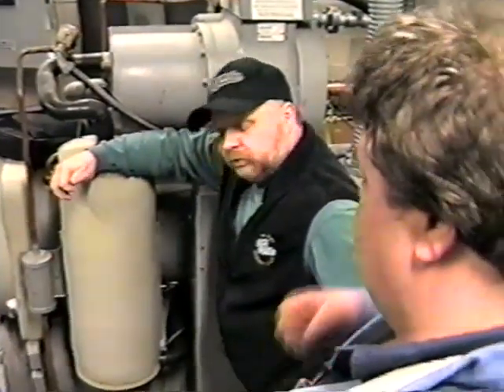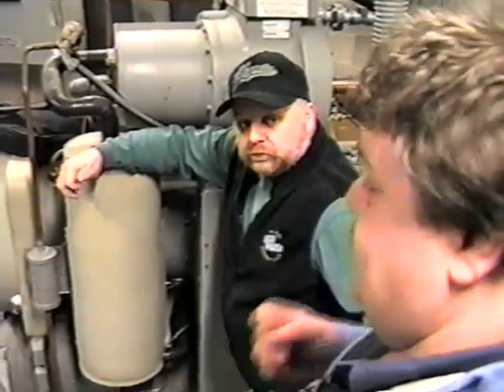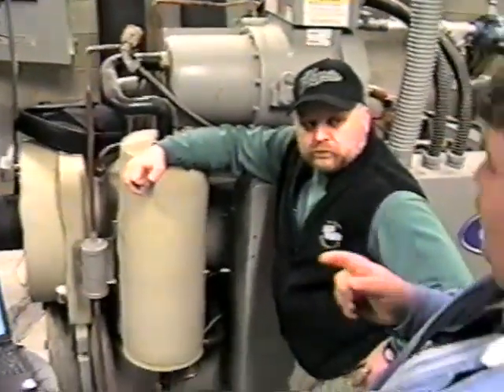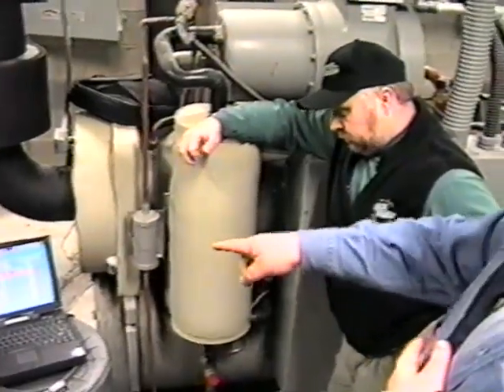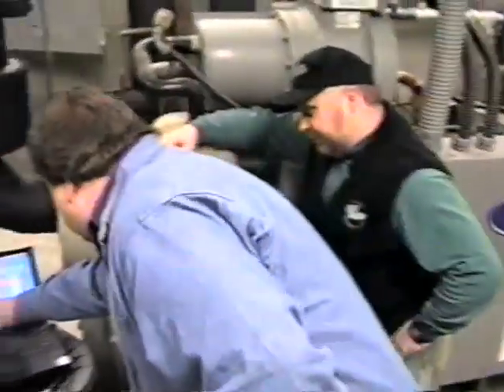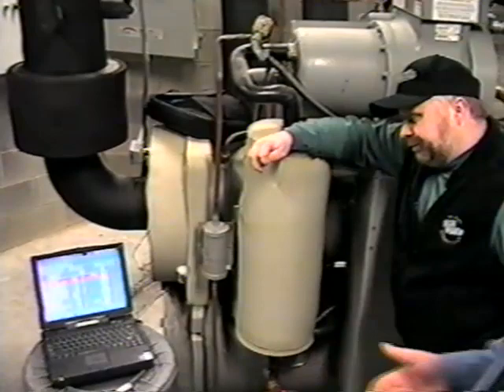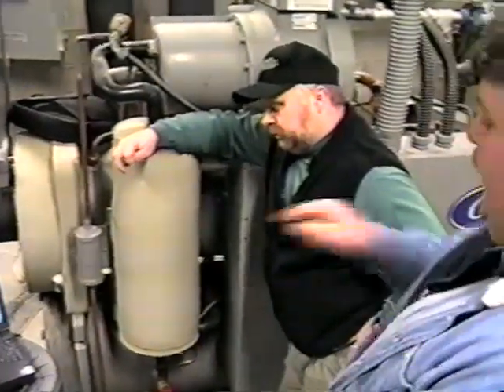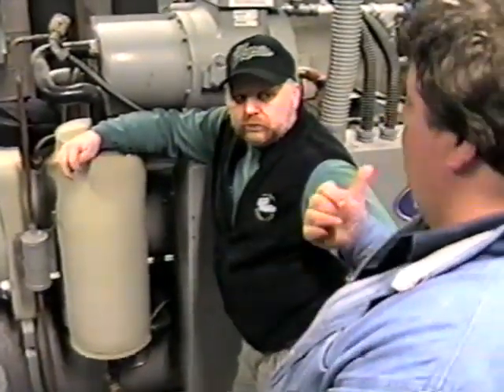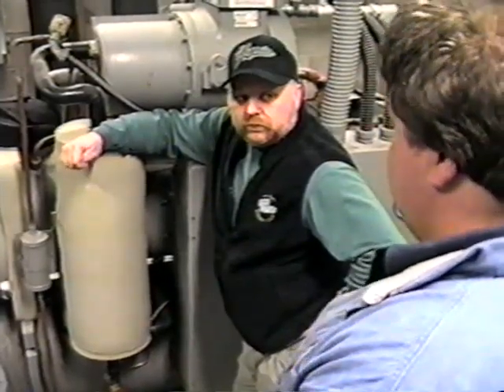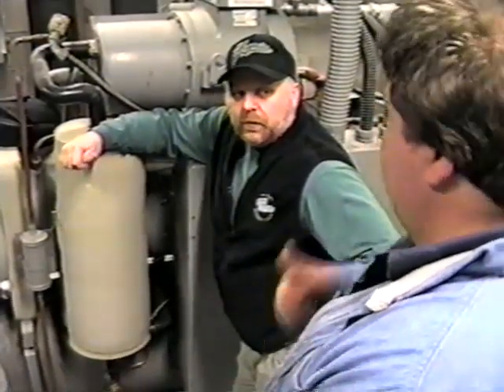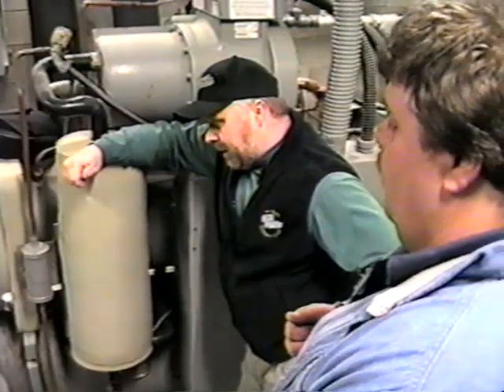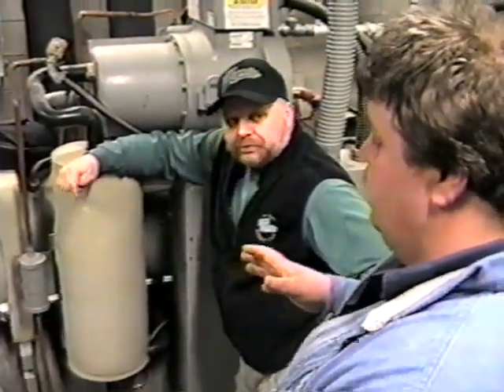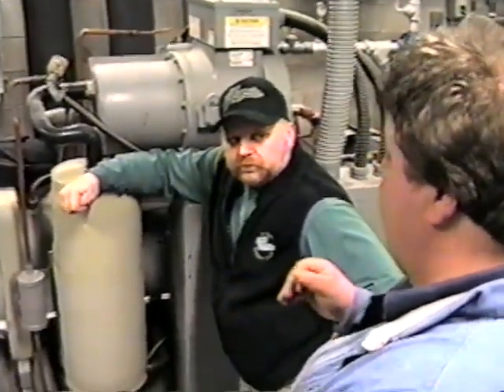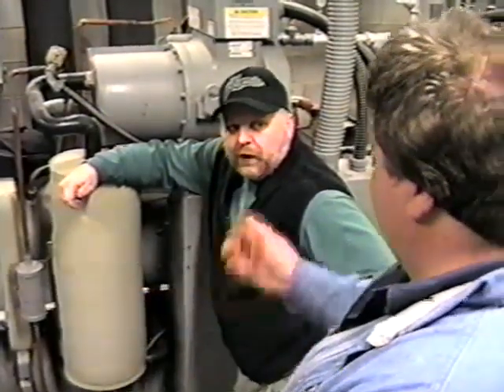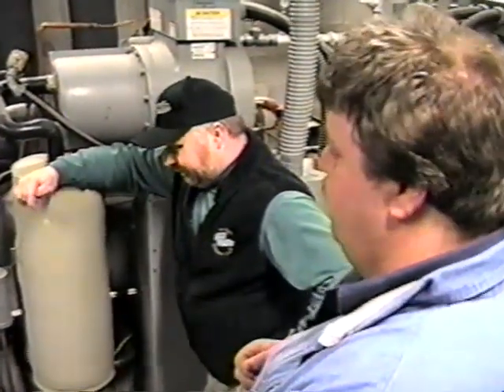That means there's an inhibit on it and it's not going to be allowed to start, even though, let's say, it's still looking for the 55 degrees. Right here, it's still below it. It's looking for heat, but I'm not going to allow that to happen until my primary thing that I want, my sump water temperature, comes up above 70. There's a little differential in there, so it's actually about 75 degrees before that control will come off and let it function properly.